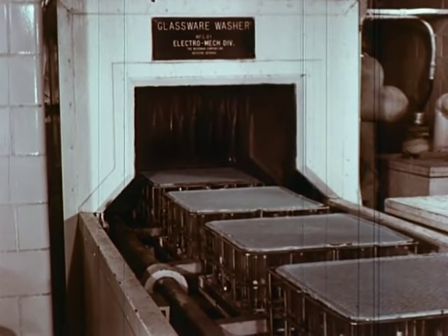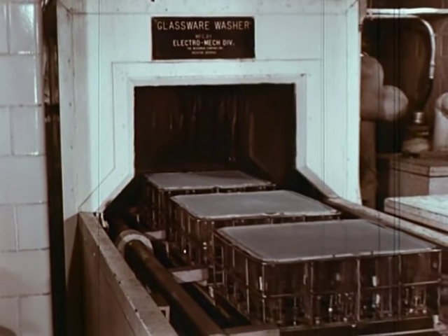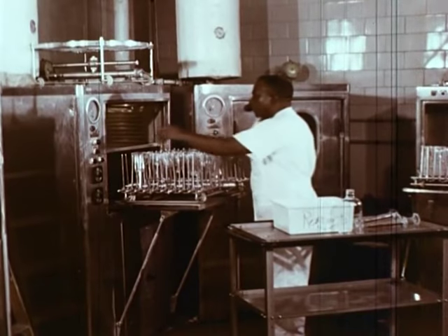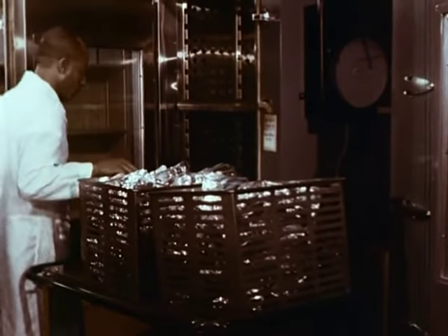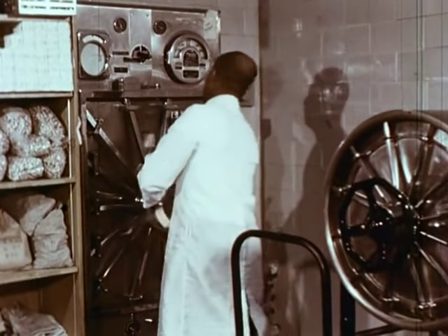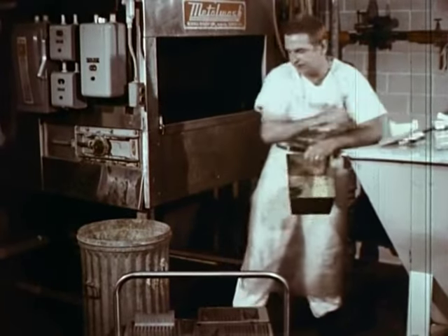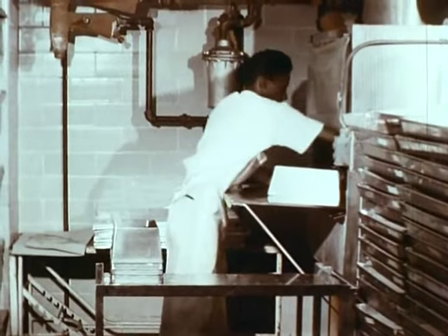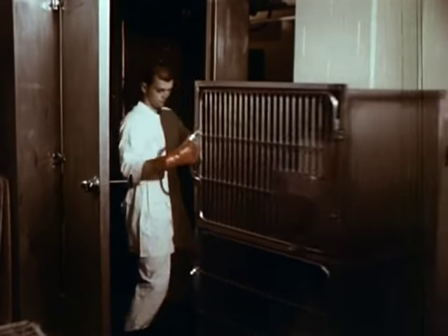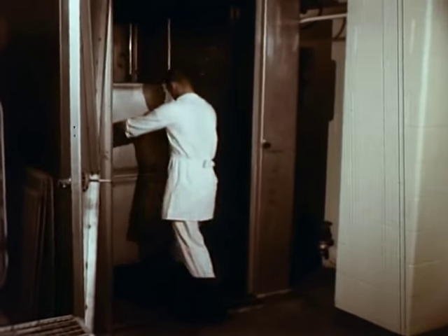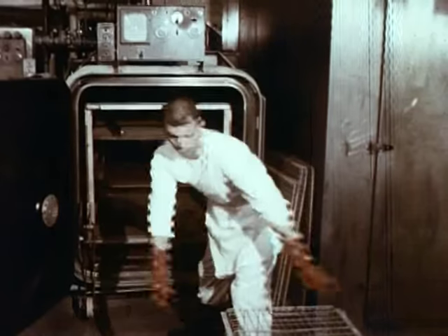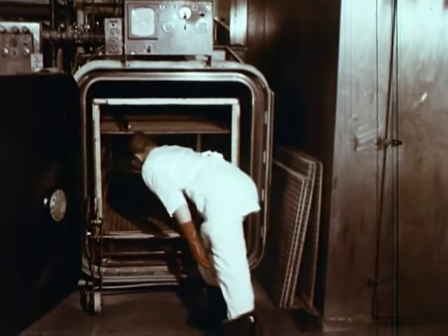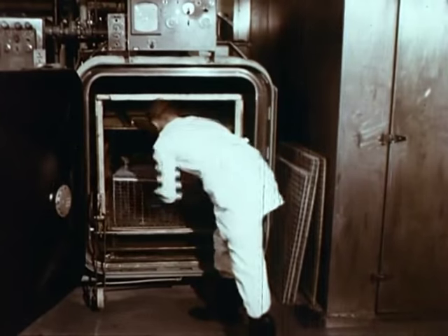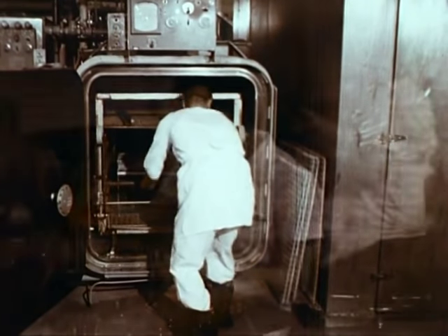In glass washing, non-contaminated glassware may be processed either in a tunnel-type machine that allows for an automatic continuous flow of items, or a batch-type washing unit for small amounts. The sterilization equipment needed in lab support consists principally of dry heat ovens and steam sterilizers. In the cage washing room, small animal cages may be processed in a continuous flow tunnel-type machine. Where larger units are processed, a batch-type washer with multiple or rotating spray heads often is used. When the cage debris contains highly infectious organisms, the cage with its debris should always be sterilized before it enters the lab support area.